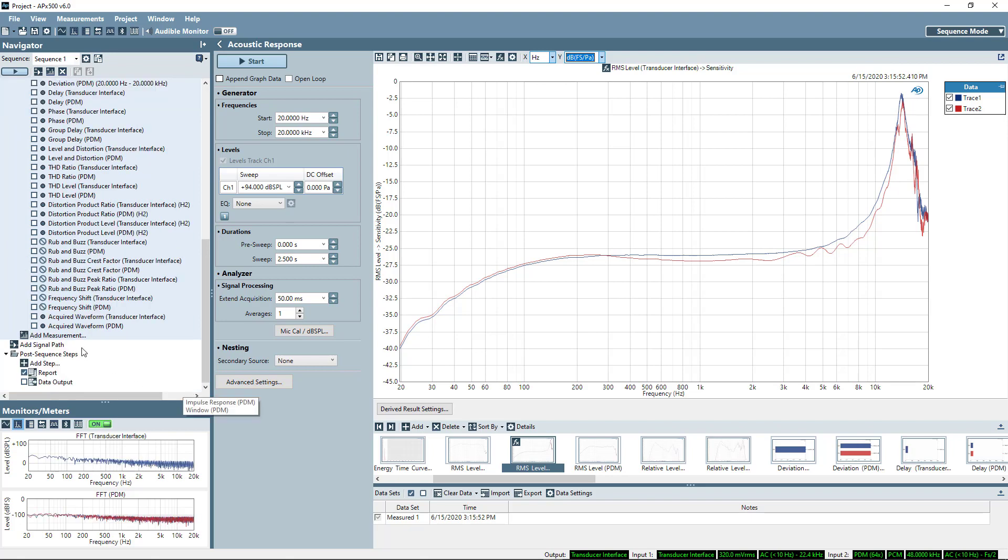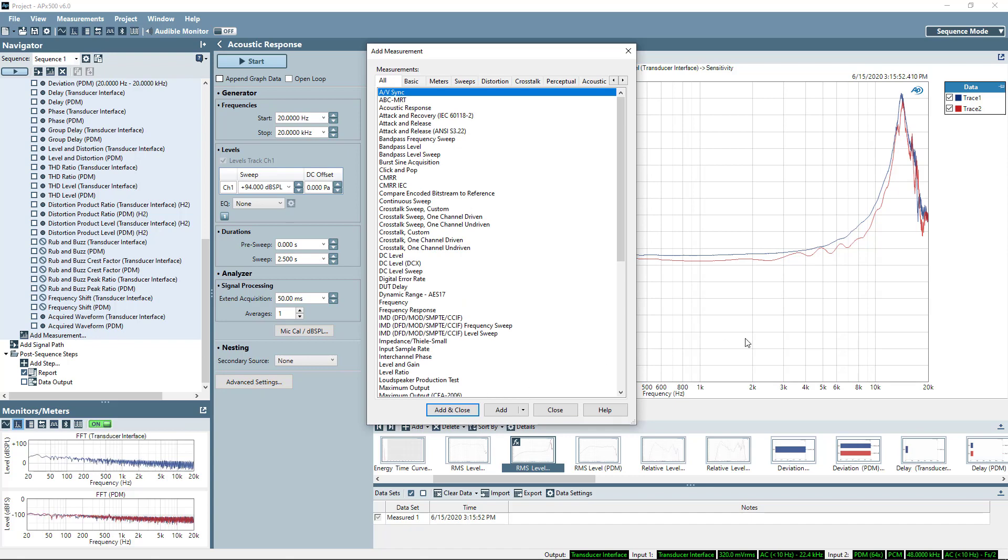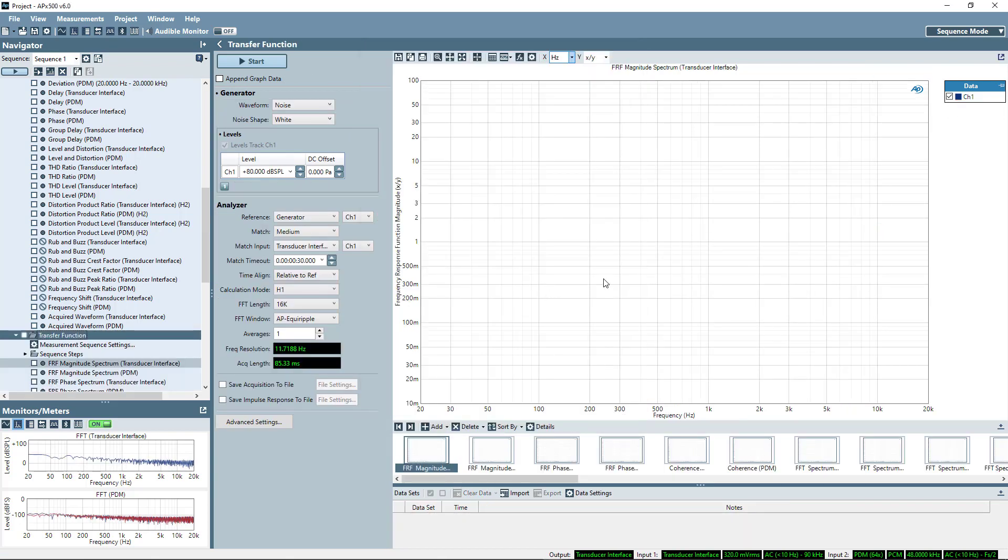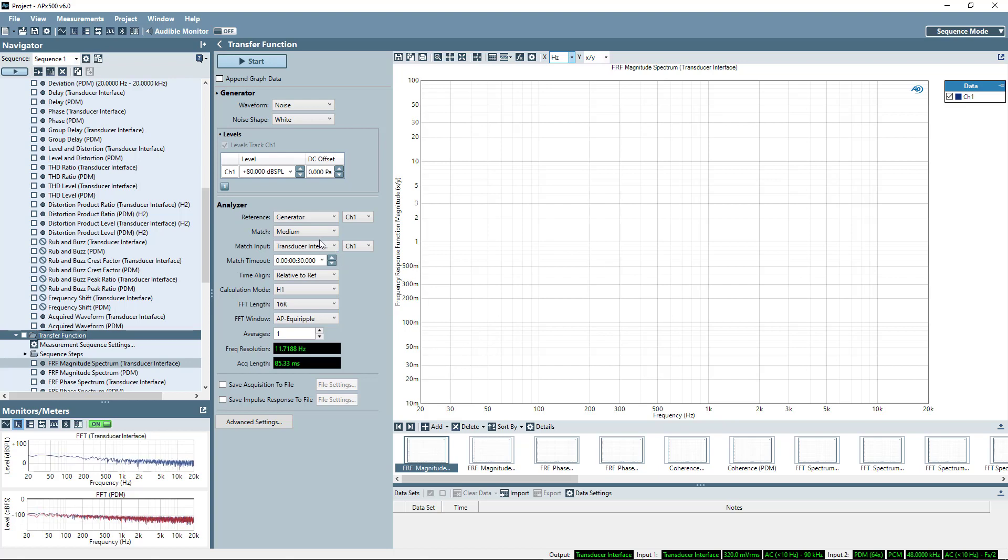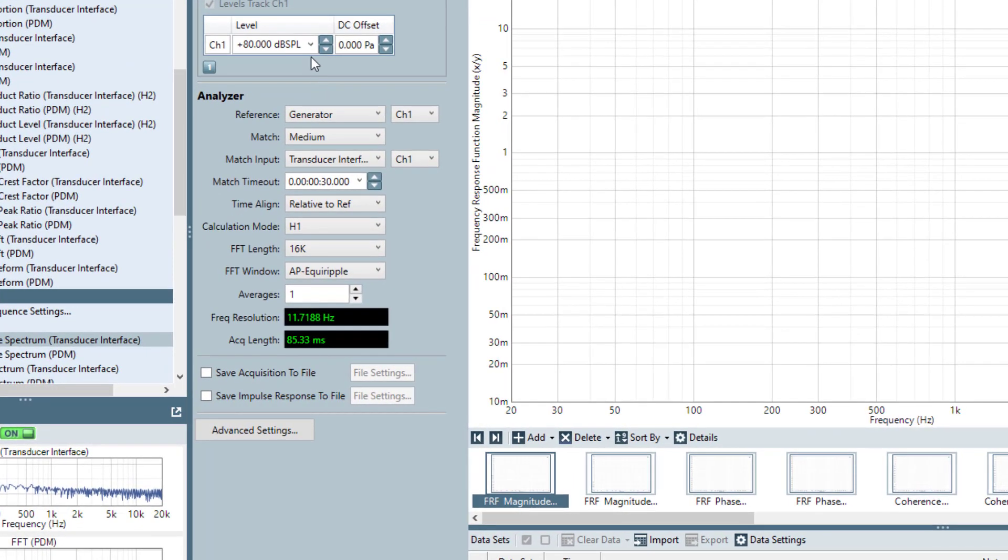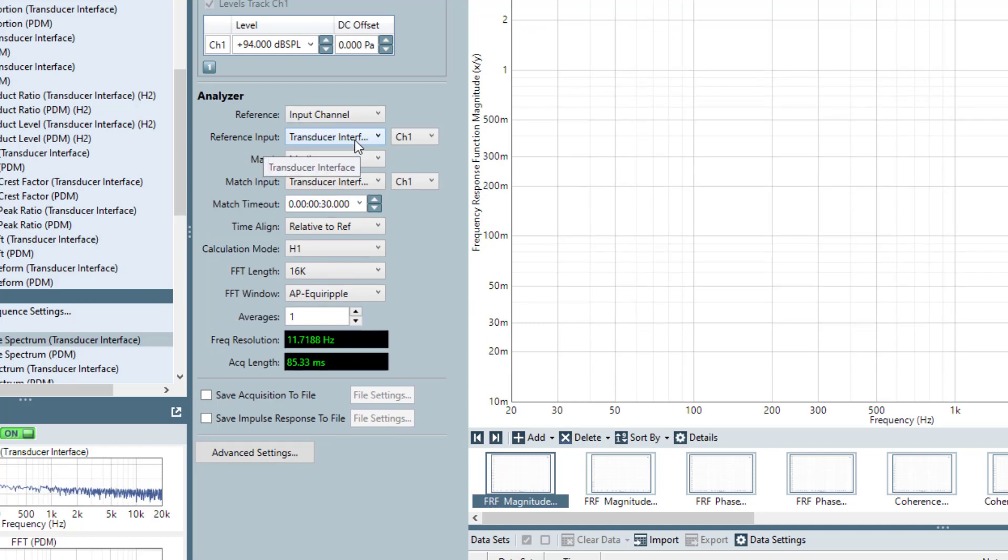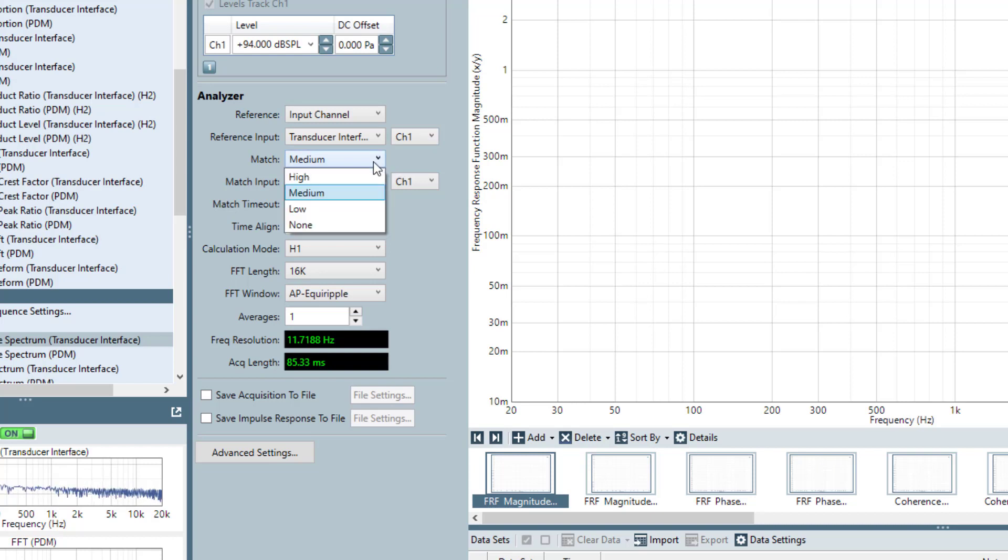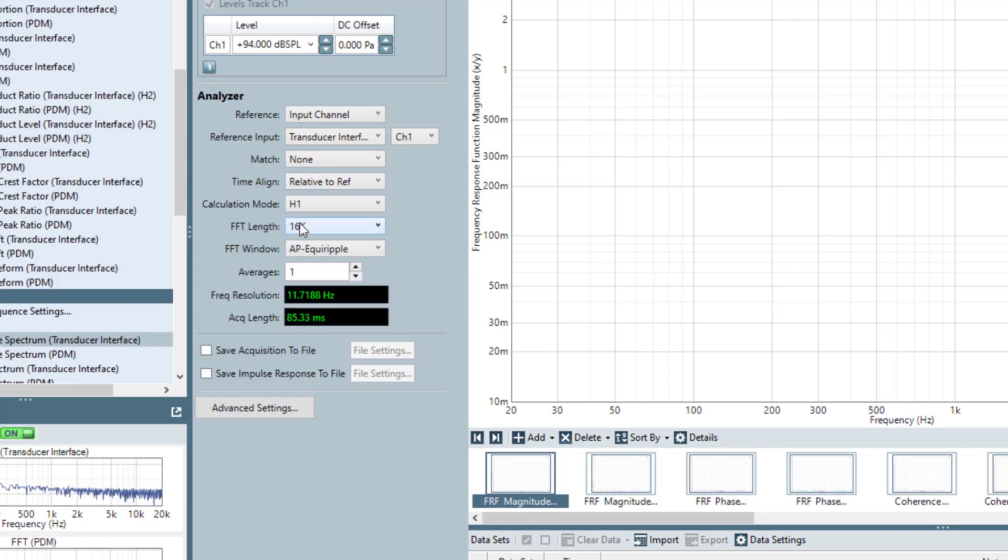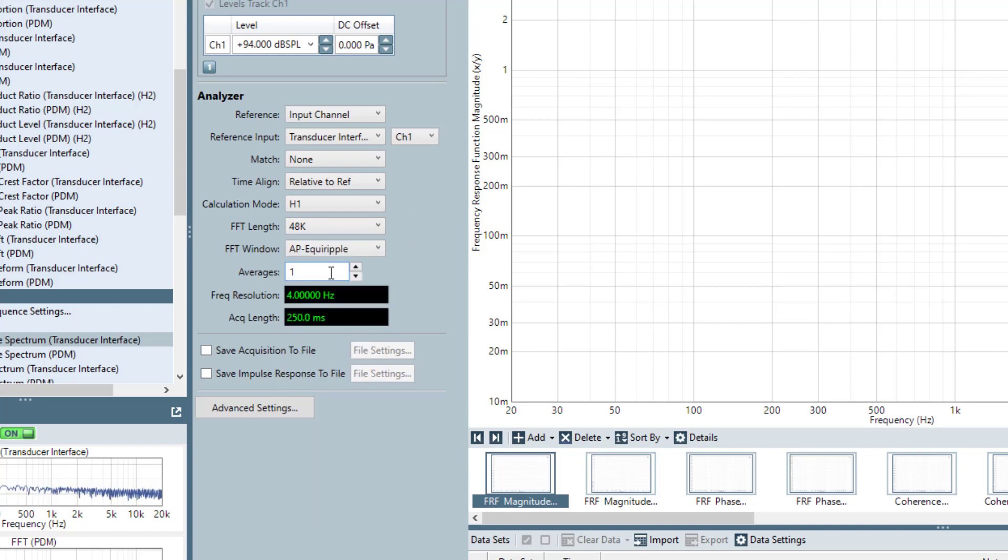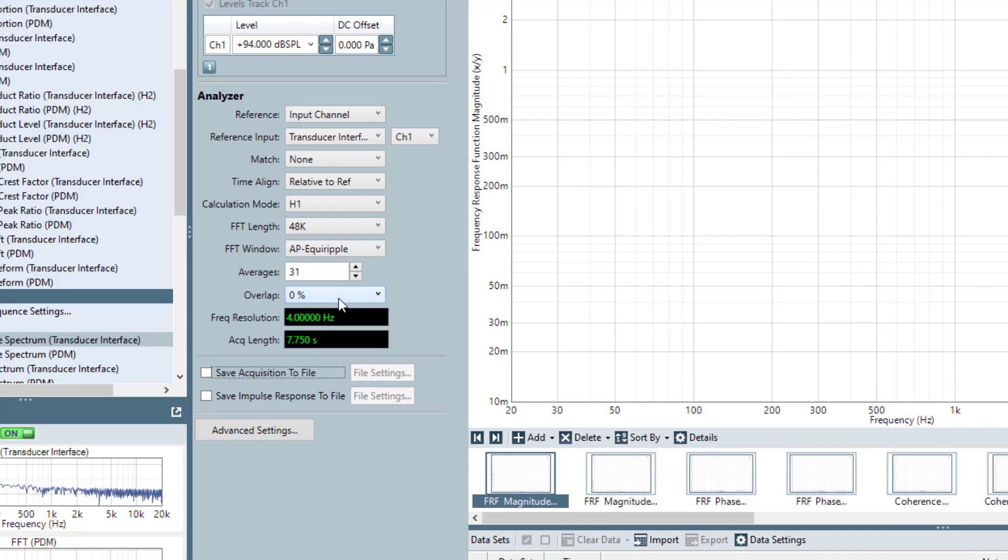Next, what I'll take a look at is transfer function. So we'll start out in transfer function. And in many ways, it's going to be similar to acoustic response. But here, actually, instead of setting a derived result, I'll say that I want to generate the transfer function directly by reference. So the reference now, instead of being the generator, will be an input channel. And I'll say the reference is going to be the transducer interface. I don't need any match because these are both closed loop measurements. Time alignment will be relative to the reference. And let's go ahead and do 48k FFT for 4 Hz resolution. And let's do 31 averages with 50% overlap.